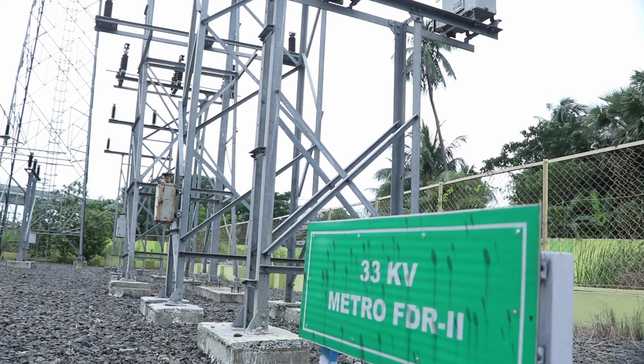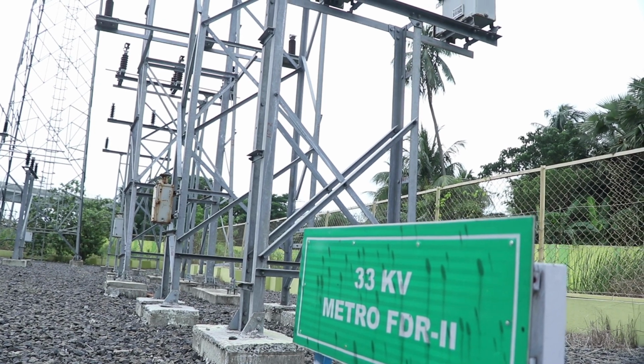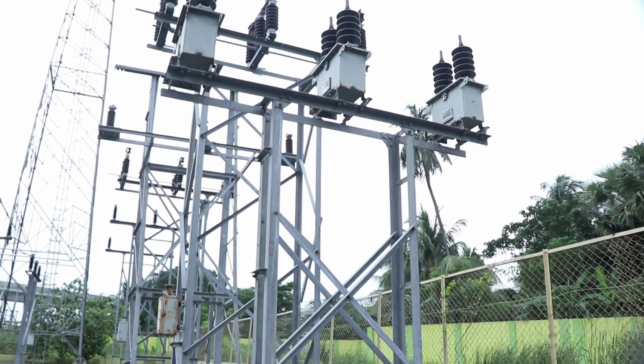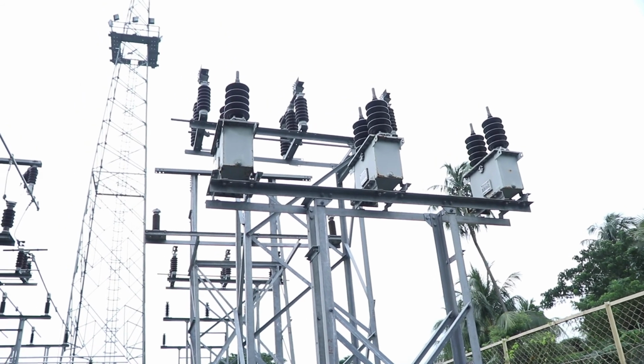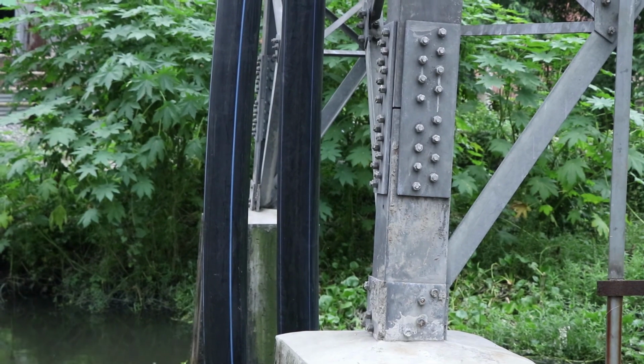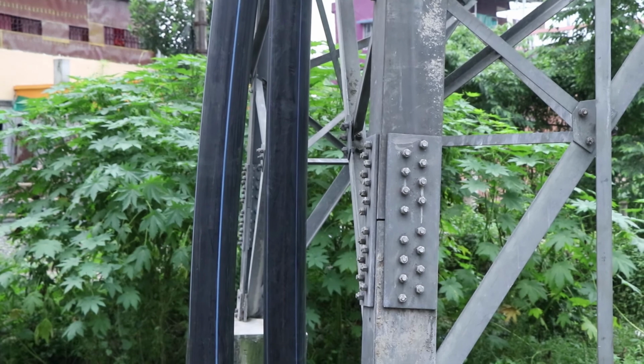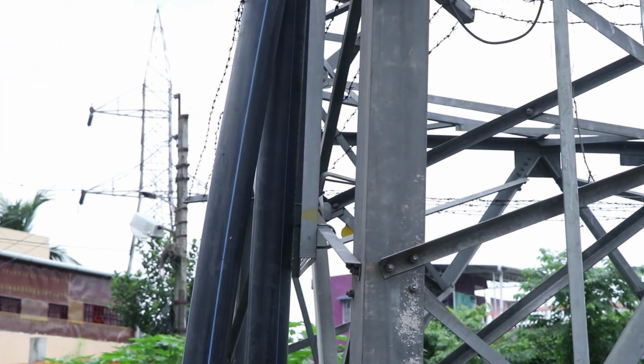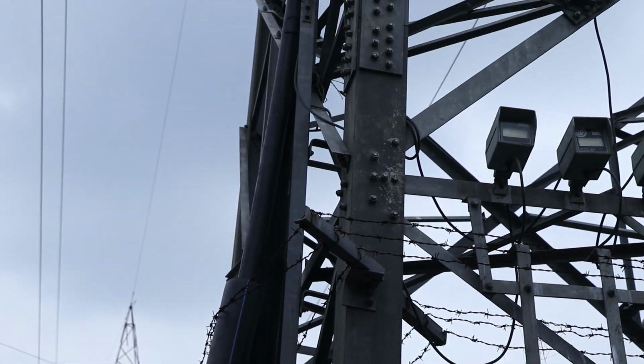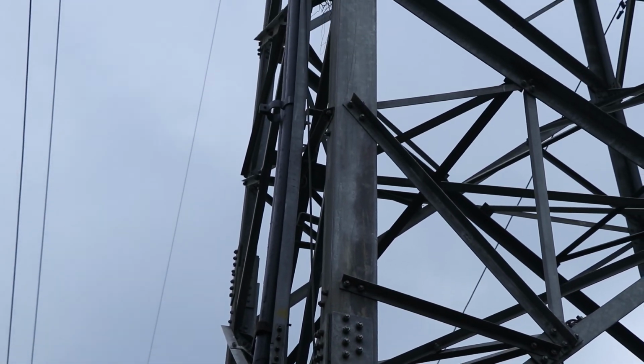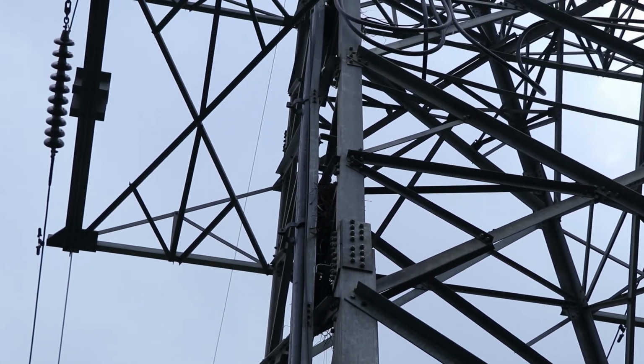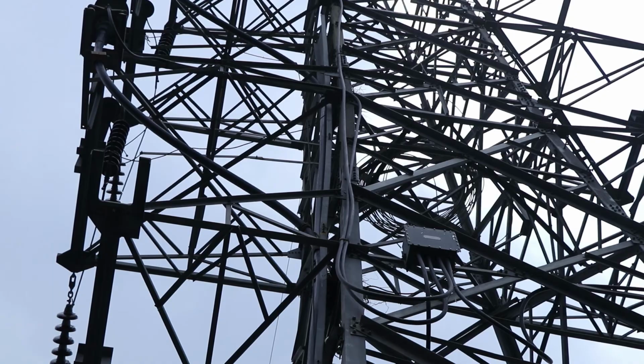To facilitate the ongoing metro project, we have diverted all our 132 kV feeders through XLPE underground cable. We have constructed a special type of narrow gauge composite tower, which is first in Eastern India of its kind, for XLPE cable and overhead junction.